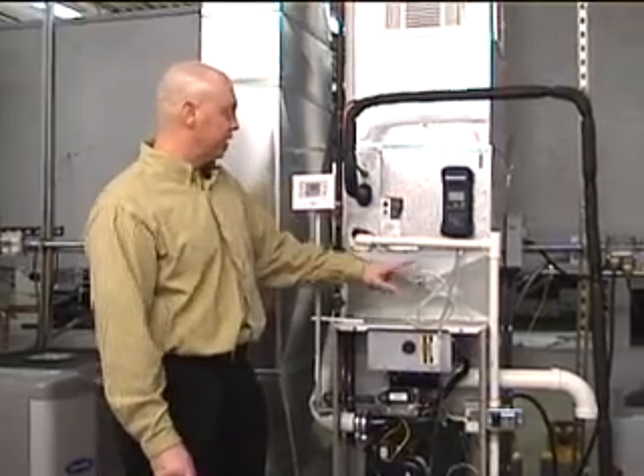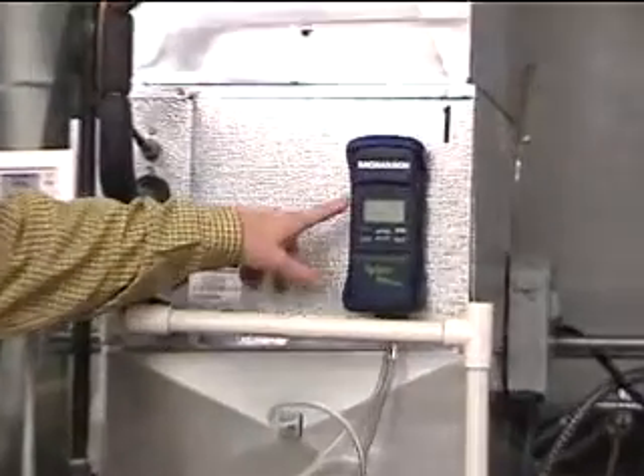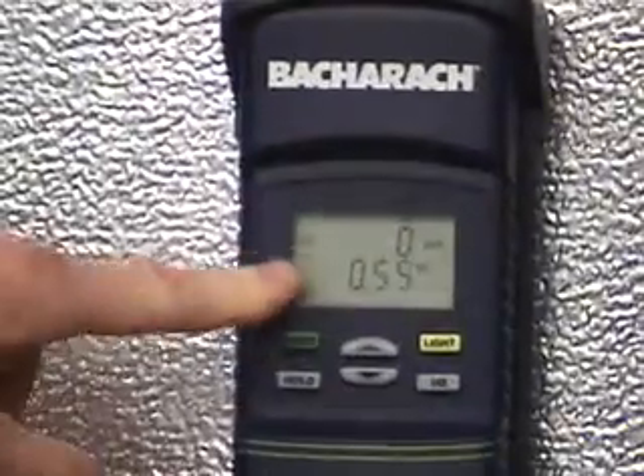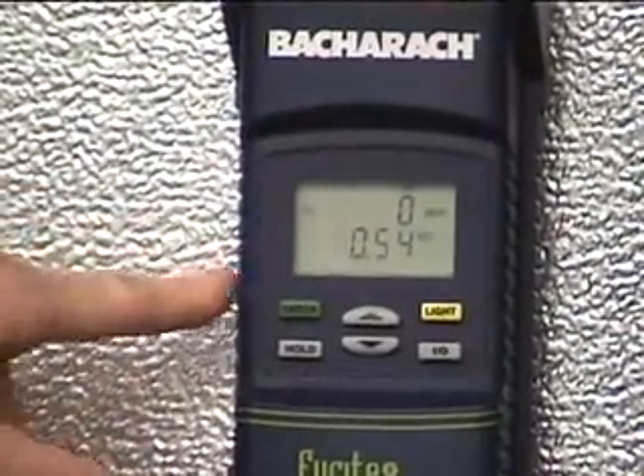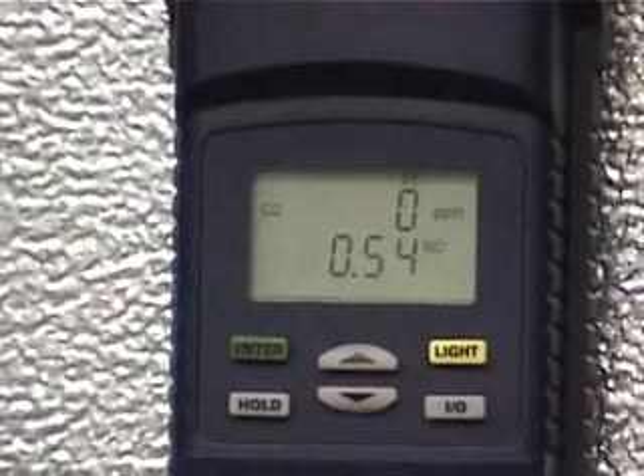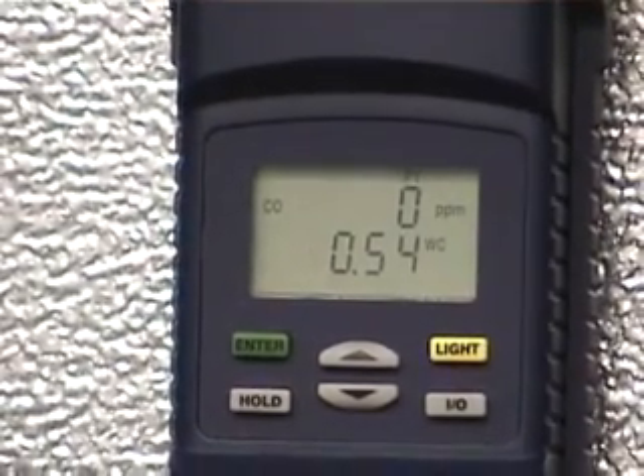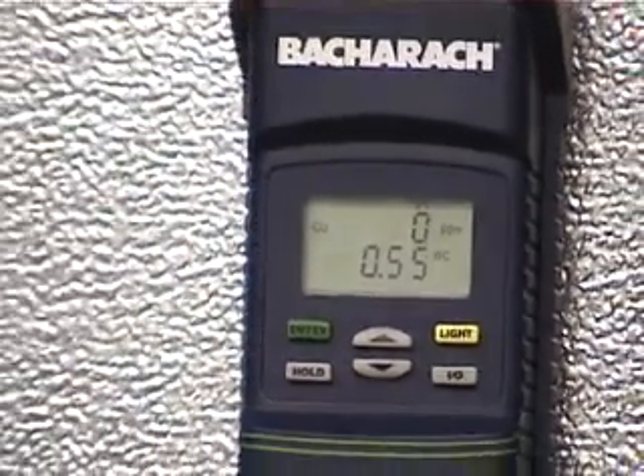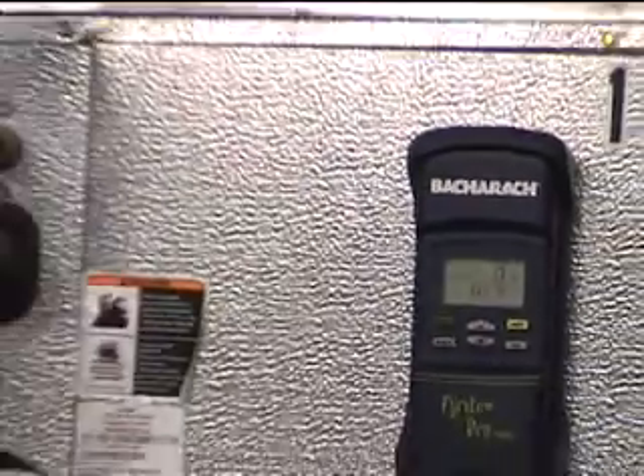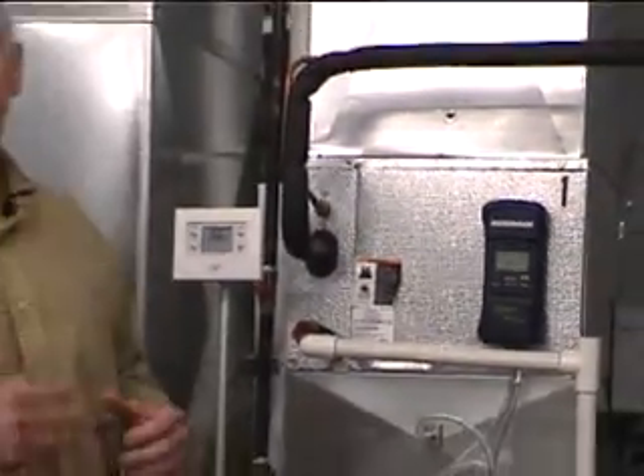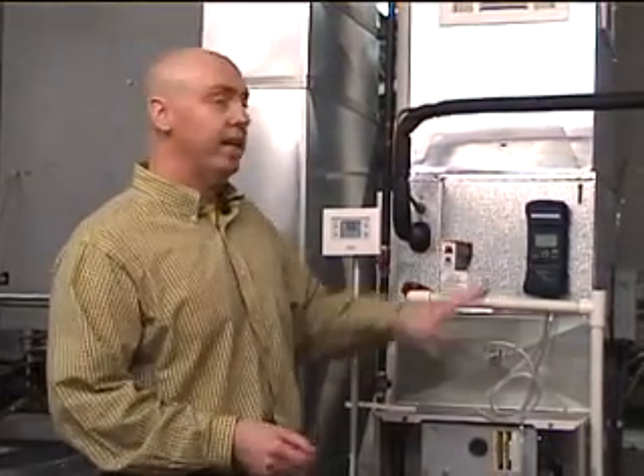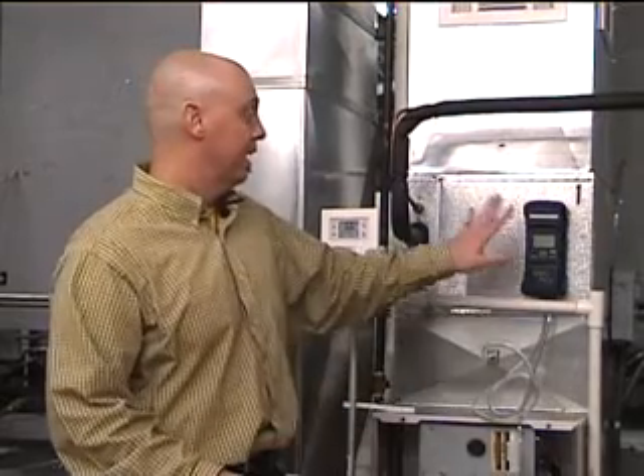So in this particular system, I am running right now a total static pressure, ESP, of 0.55 inches of water column, which is slightly above what our maximum allowable level is for this furnace. I am running continuous fan right now. On this particular piece of equipment, the continuous fan mode happens to be the low heating speed, so I am actually running too high. There is too much resistance in this duct system. Remember what I said earlier: when you're in heating, you want that number to be a little bit lower, because the 0.5 inches of water column that they typically rate for residential equipment is a cooling number for maximum levels.